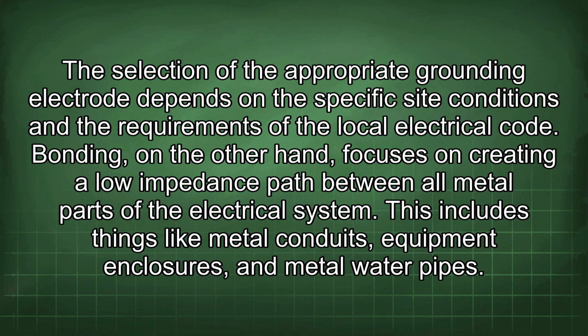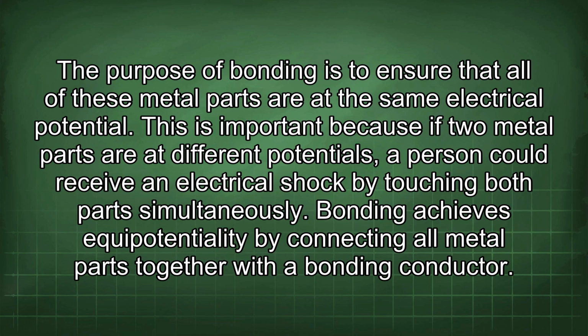code. Bonding, on the other hand, focuses on creating a low impedance path between all metal parts of the electrical system. This includes things like metal conduits, equipment enclosures, and metal water pipes. The purpose of bonding is to ensure that all of these metal parts are at the same electrical potential. This is important because if two metal parts are at different potentials, a person could receive an electrical shock by touching both parts simultaneously. Bonding achieves equipotentiality by connecting all metal parts together with a bonding conductor.